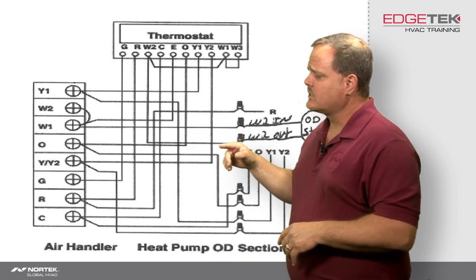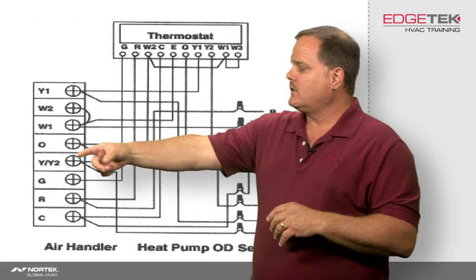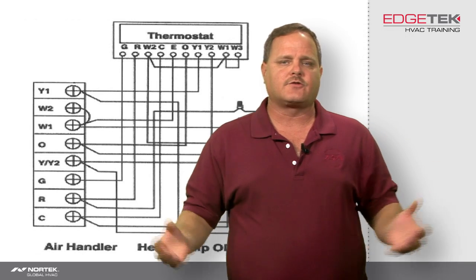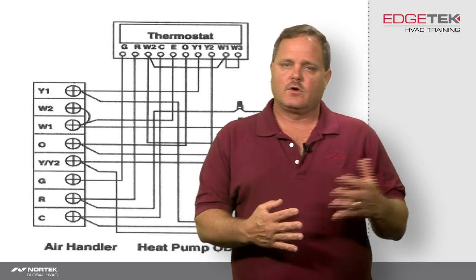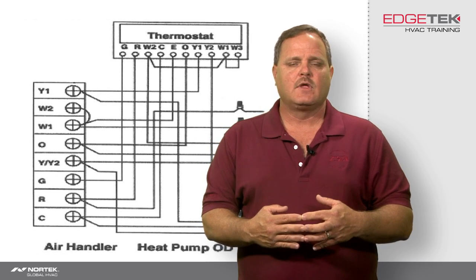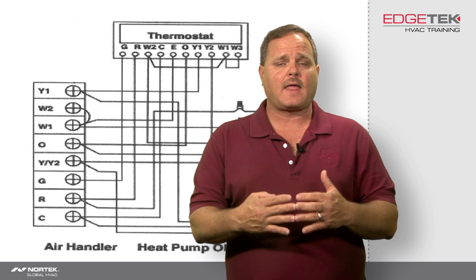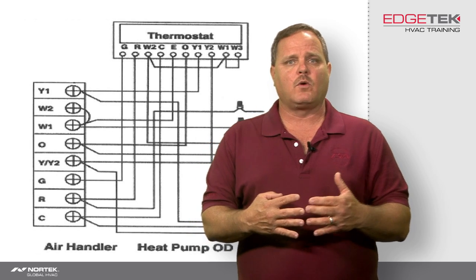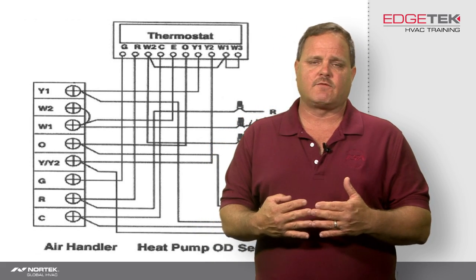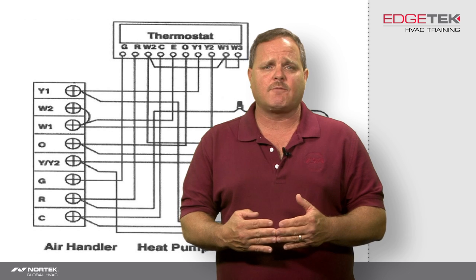One more thing to cover: if we're only using a two-stage capable thermostat with a two-stage heat pump, you may need to jump W1 and W2 together on the indoor unit in order to get all the electric heat to function. On our newer air handlers, if you don't energize W2, depending on how many kW, it may not turn on all the electric heat. The last page of the installation instructions on our air handlers gives you the sequence — how many banks of electric heat come on depending on whether you have W1 only, or W1 and W2. I hope you found this tech tip useful. Keep tuning in to edgetechhvac.com for more useful tips.